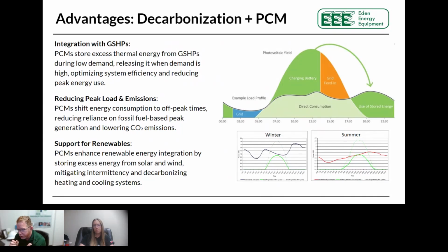From a reducing-peak-load standpoint, if we put in a heat pump — water-to-water geothermal, or I'd also say air-to-water — we can run it off-peak, take full advantage of low utility rates (in Ontario as low as 2.4 cents a kilowatt), store it in the thermal battery, and use that battery when it's on-peak. Reducing peak load is fantastic.